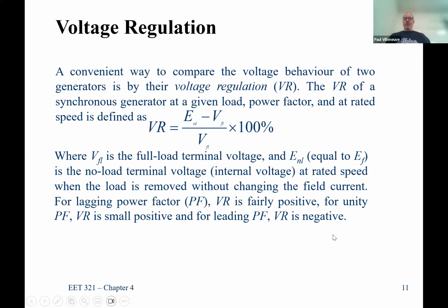So if you look at the description here, let me move this out of the way. It depends on the power factor. If you have a lagging power factor, your voltage regulation is going to be positive. If it's a unity power factor, which means no reactive power is going in or out of the machine, it's going to be positive, but very small, almost negligible. And if it's a leading power factor, which means reactive power is coming in from the grid, then our voltage regulation is going to be a negative value.